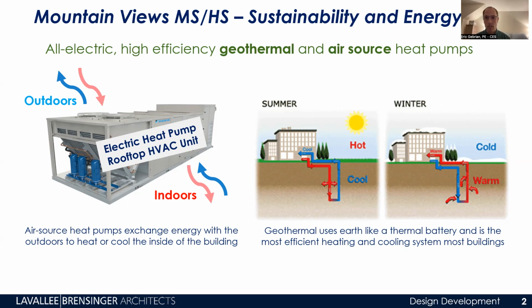So the proposal is: if we cut the geothermal wells in half, roughly, that saves a large chunk of money on construction. We still have half of our HVAC using geothermal, which is the absolute most efficient way to heat and cool. The other half uses what we call air source heat pumps. Still a heat pump technology, not quite as efficient as geothermal, but pretty close, so we're not really taking a huge energy penalty. It's on the margins.